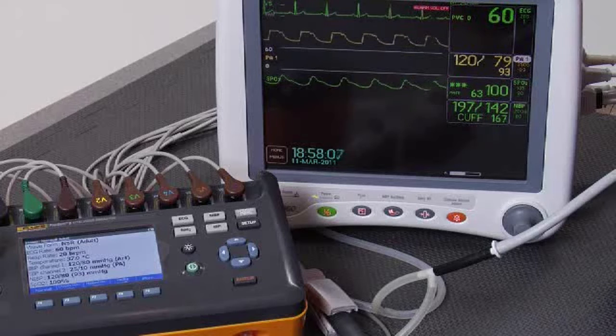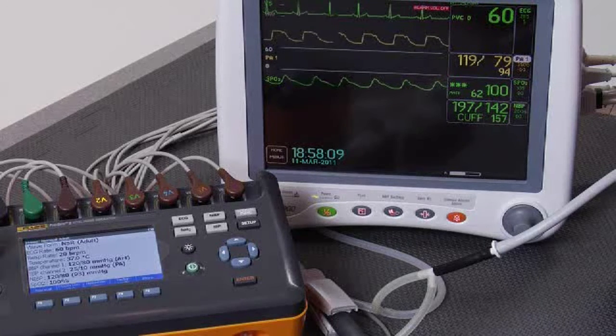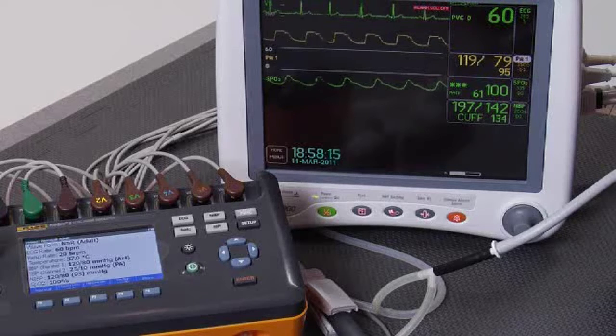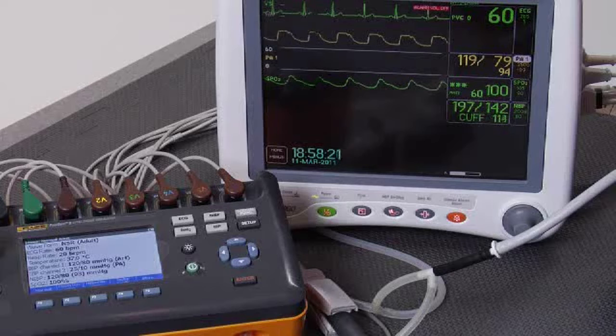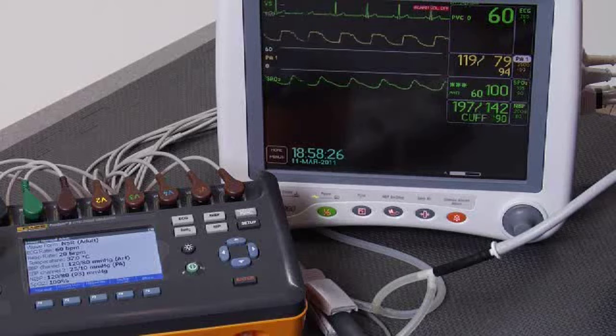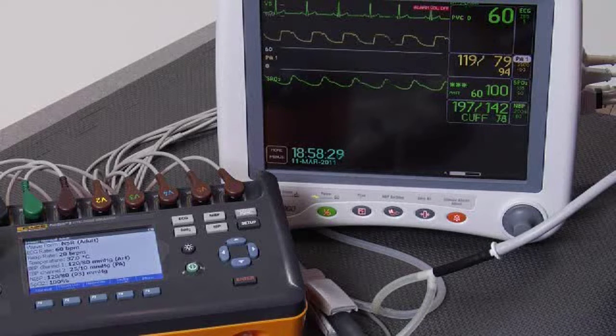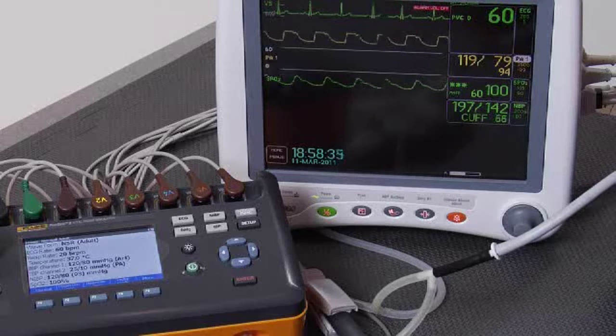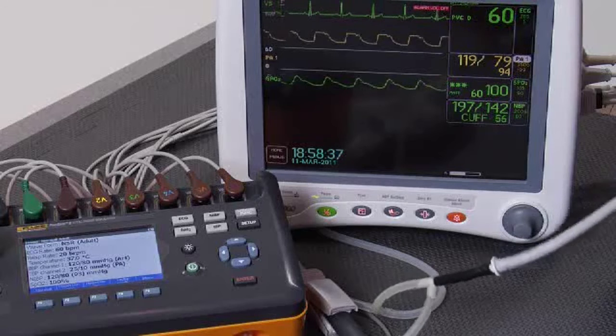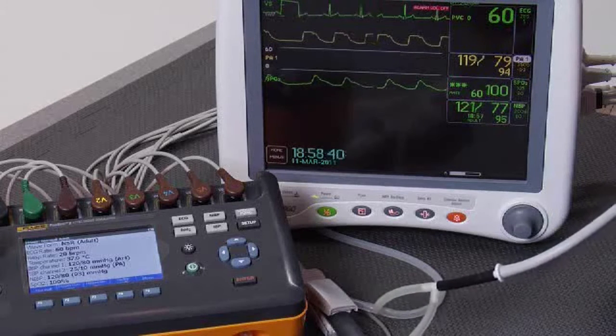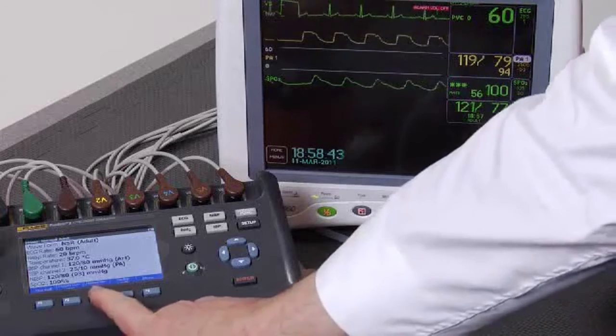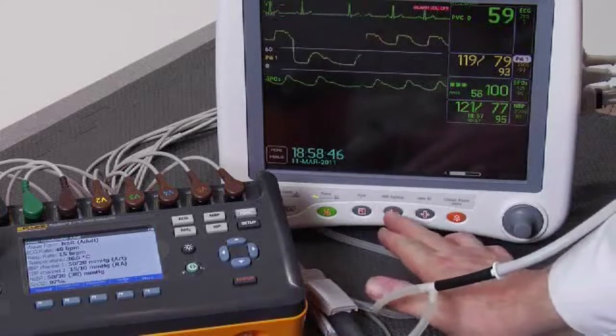As you can see, the patient monitor is already displaying 60 beats per minute for heart rate. It's gotten 119 over 79 with a mean of 93 for invasive blood pressure. And the cuff is making its measurement now for the NIBP reading. O2 sat is 100%. There we go, 121 over 77 versus 120 over 80, pretty good. We'll go to hypotensive now and start another cuff measurement.